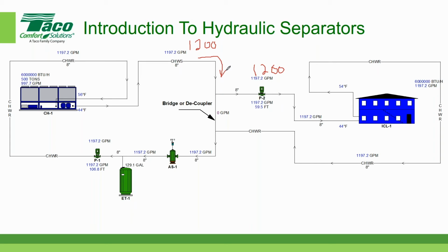And because the secondary pump is pumping 1,200 gallons per minute, it's going to draw off 1,200 gallons per minute in this direction. Eventually it's going to satisfy the load in the building, and then it's going to come back here. Because there are no leaks in the system and nobody is drawing off any water, it's going to come back at 1,200 gallons per minute. It's going to round the corner here to go back to our chiller at 1,200 gallons. And the flow this time across the bridge is 0 gallons per minute.